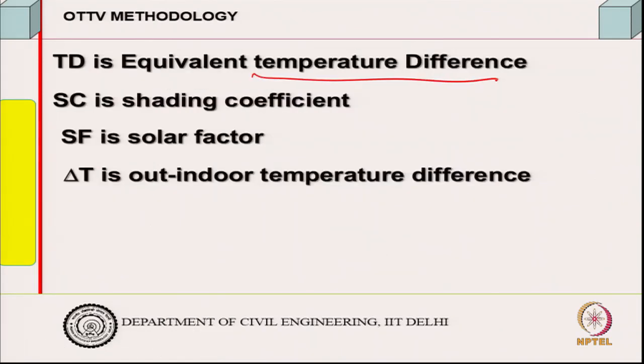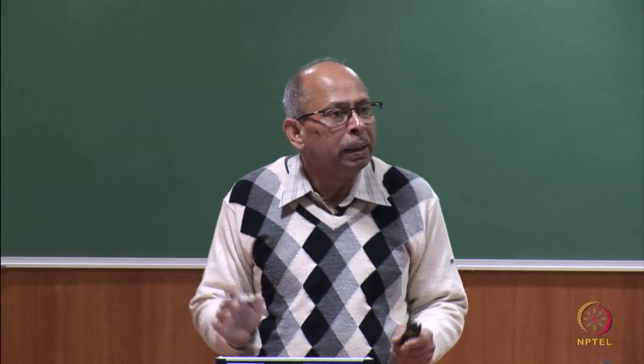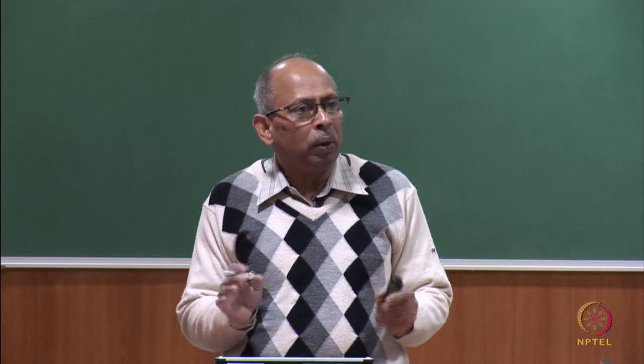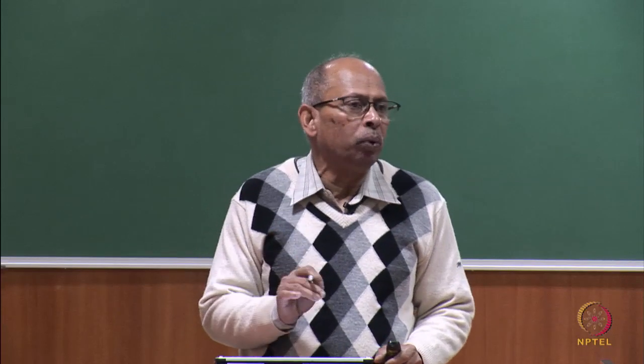U values, one for the solar gain of the skylight, this solar coefficient, shading factor, this is what is taken into account. So this is the formula. TD is the equivalent temperature difference, calculated over the years, obtained through regression, and these are given in the code.